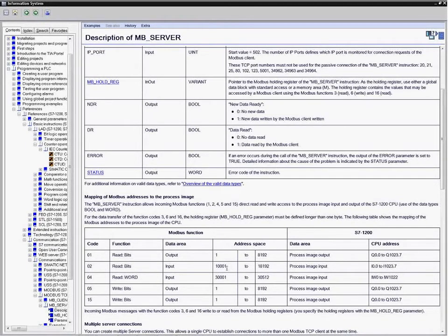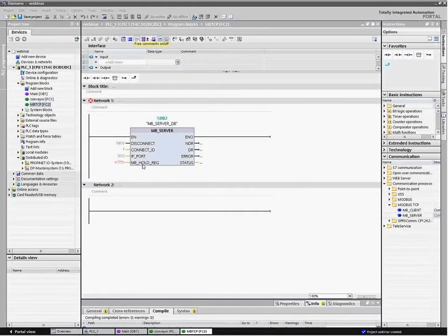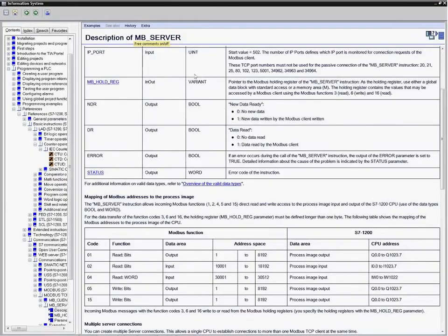Modbus registers in the 10,000 range are input areas. The 30,000 registers in Modbus are typically analog inputs, and they're going to be pre-mapped automatically. For outputs, there are ways of writing multiple bits, and these are just Modbus function codes, but they're going to the same addresses. So we've already implemented Modbus to a certain extent. The thing left for us to do now is what's called the holding registers. And the holding registers, as I mentioned, are user-defined areas.